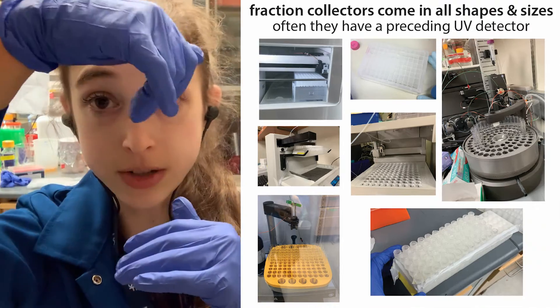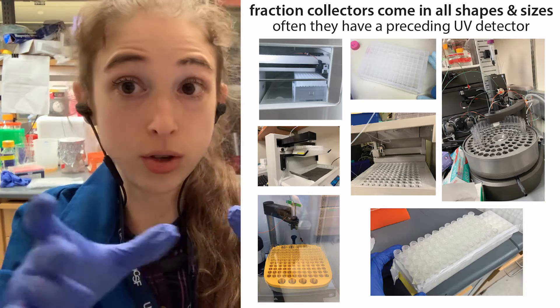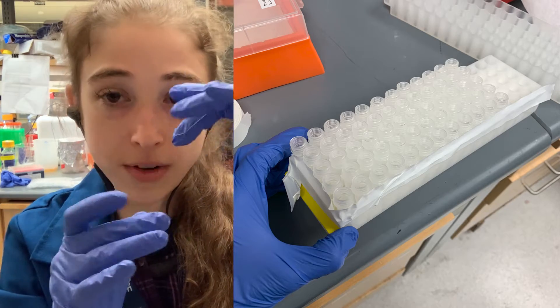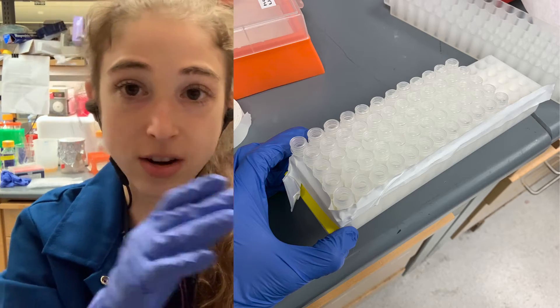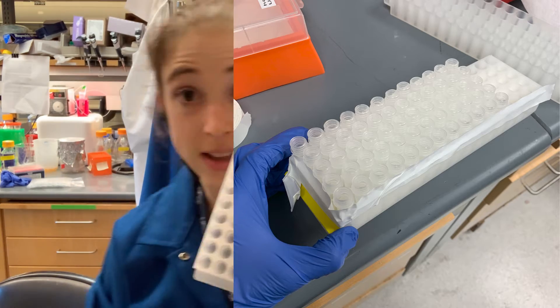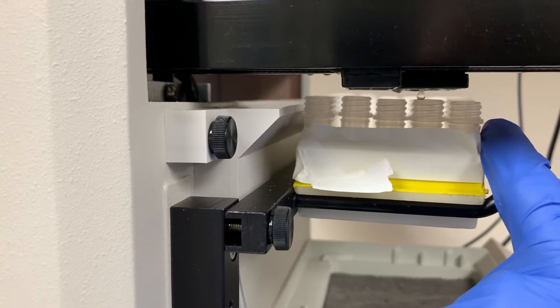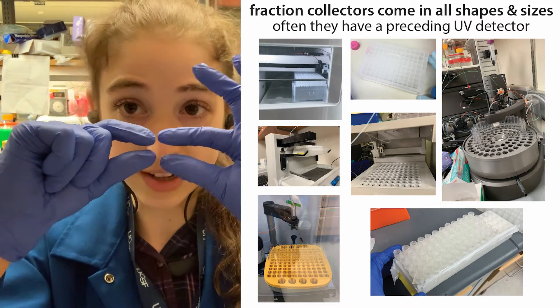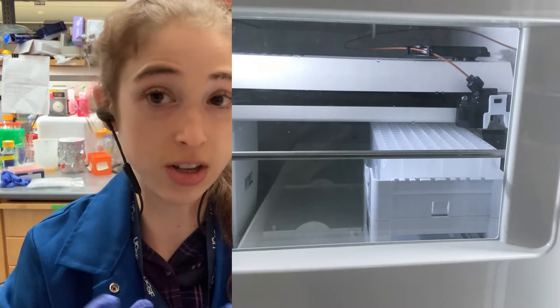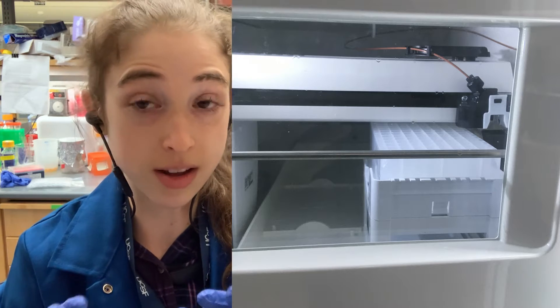Make sure that when using an automated fraction collector, it can have trouble depending on whether it's fully automated or whether you have individual tubes — I've had trouble where the fraction collector goes between the tubes or has a hard time shifting over. If you have one of those where you put the tubes into an individual rack, I like to tape it down because those tubes can float out and move around, and then you'll miss the fraction collector, which is not fun. Also make sure the collector is giving even amounts in all of the tubes. Sometimes you can get air in the system — for something like an AKTA, you can get air in your pump — which makes the fractions different sizes, and that's an indication that something is going wrong.